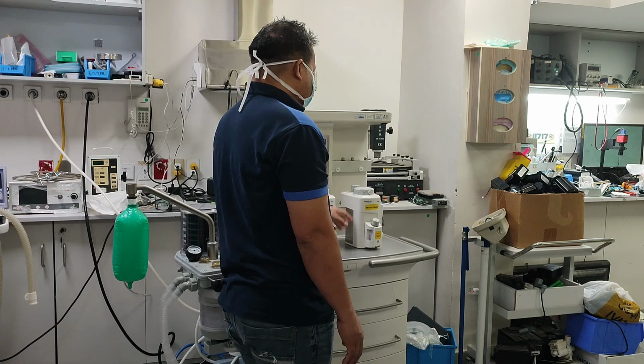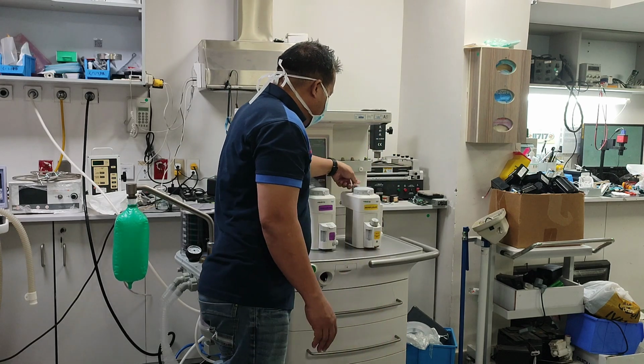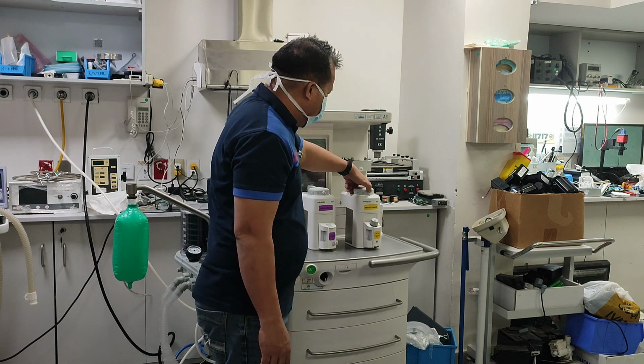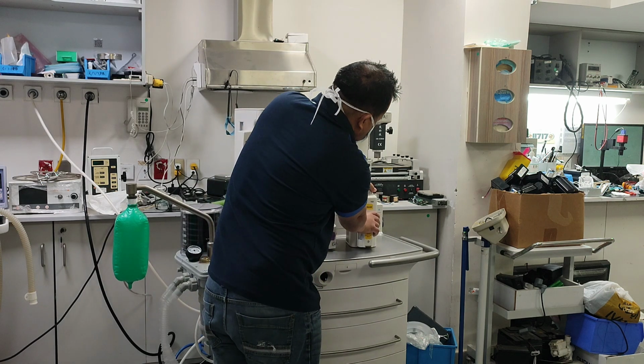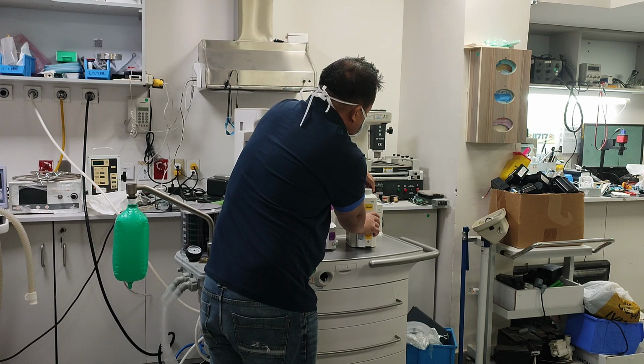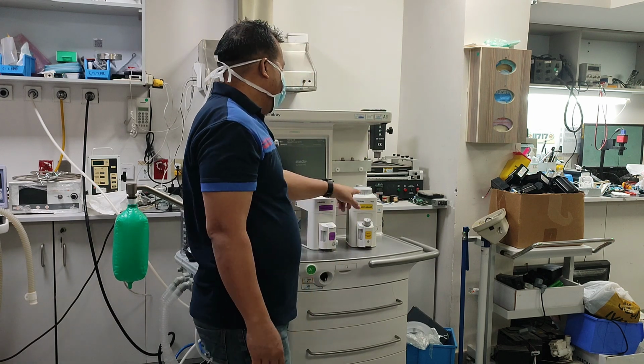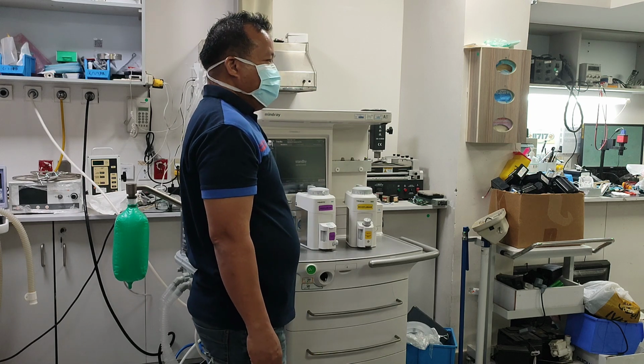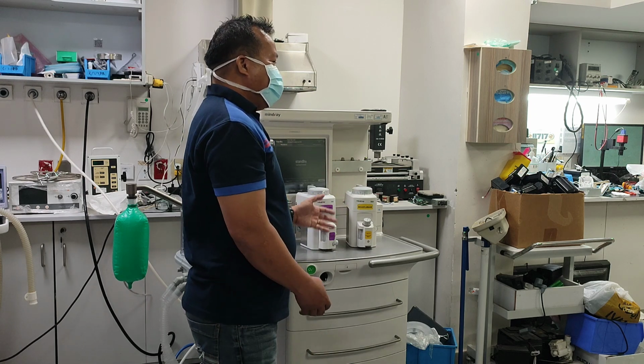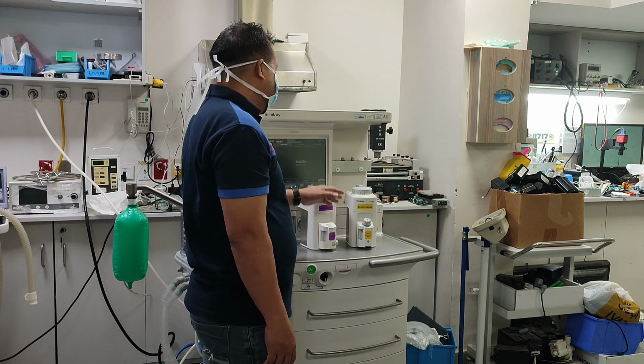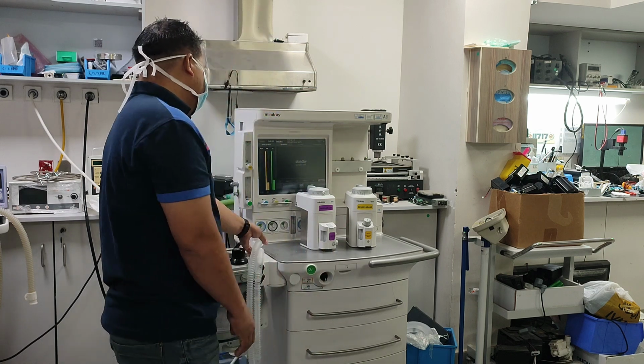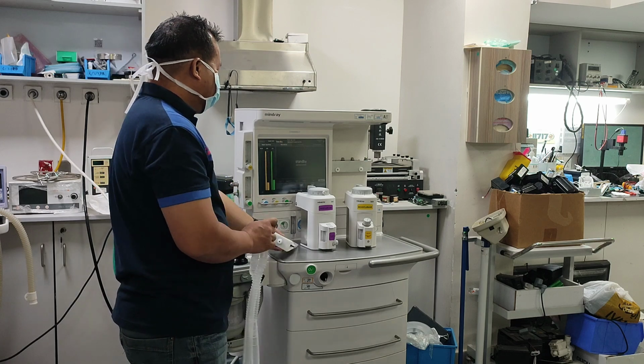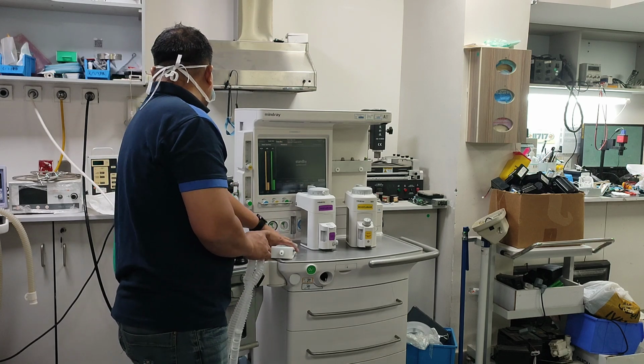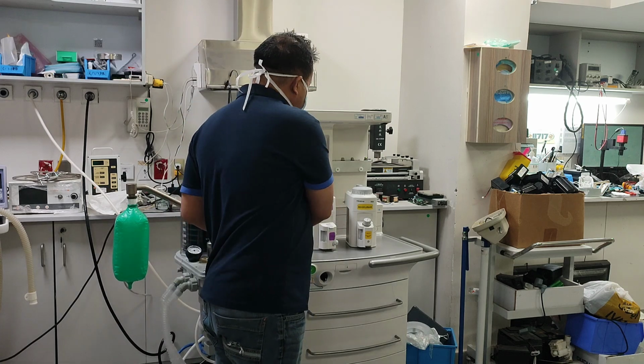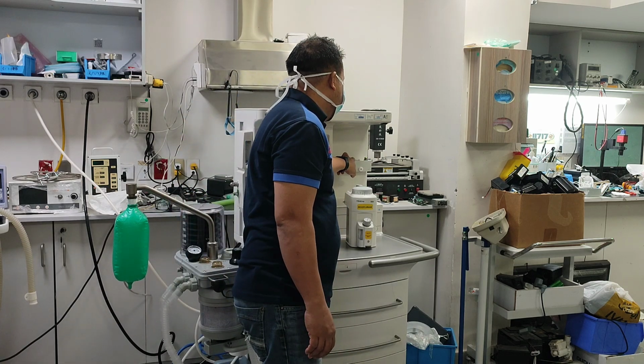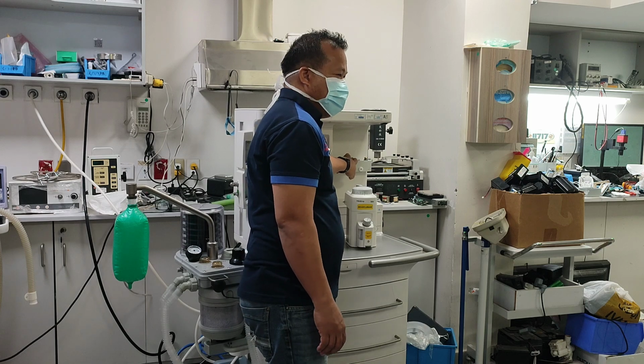This is important. Once the doctor sets, for example, 2% of gas, then they will give you only the message here, only one, meaning that some gas has leaked. It's not going to the tubing or the piping, going to this one here. It will not go here. So it's very important that this gasket here should be replaced every 6 months.